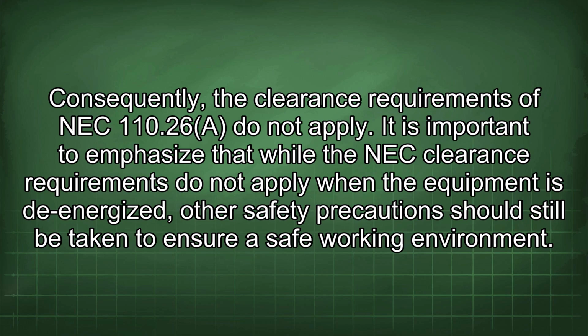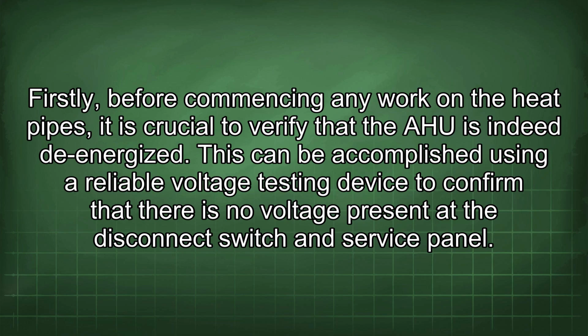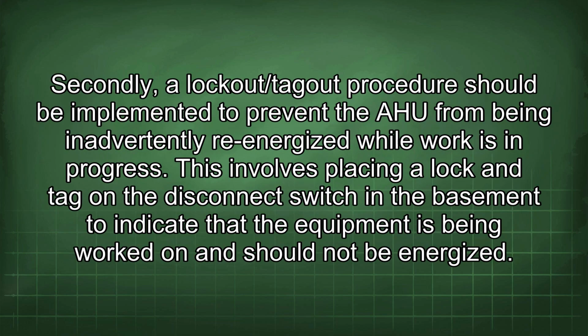It is important to emphasize that while the NEC clearance requirements do not apply when the equipment is de-energized, other safety precautions should still be taken to ensure a safe working environment. Firstly, before commencing any work on the heat pipes, it is crucial to verify that the AHU is indeed de-energized. This can be accomplished using a reliable voltage testing device to confirm that there is no voltage present at the disconnect switch and service panel. Secondly, a lockout/tagout procedure should be implemented to prevent the AHU from being inadvertently re-energized while work is in progress. This involves placing a lock and tag on the disconnect switch in the basement to indicate that the equipment is being worked on and should not be energized.